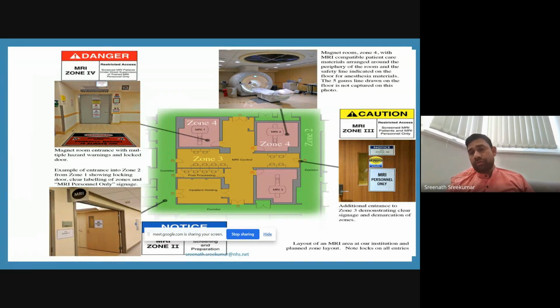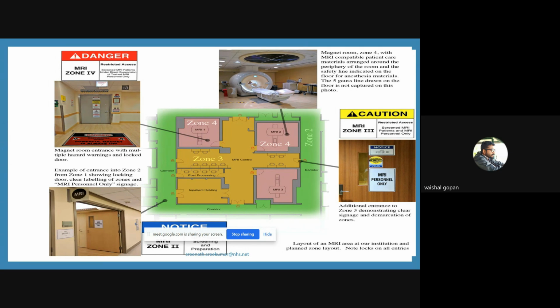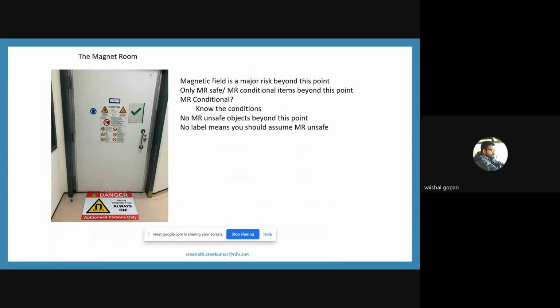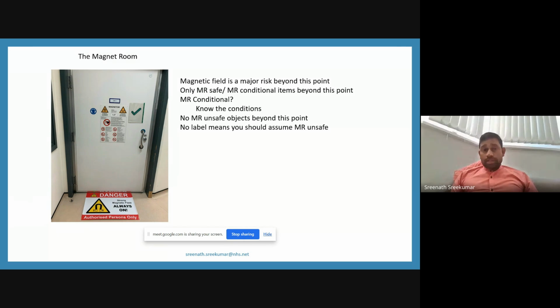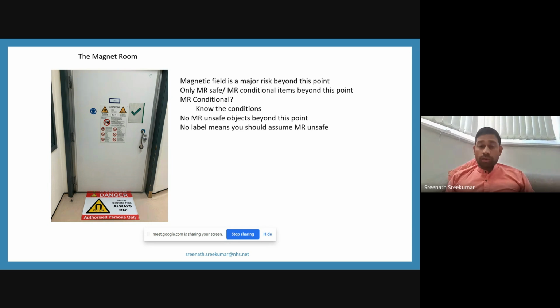The same thing, but with different terms in ACR manuals. So this again is the same thing. I'm just showing it because it's easy for people to see. The magnet is always on, even at the doors. I'm telling you all these things because somebody not familiar with an MRI scanner should think about why the MR magnet is always on. There is no stopping of the MRI magnet, and the magnet of the machine will always have the 5 gauss line. So any conditional devices or non-conditional devices going inside there carry potential risk.